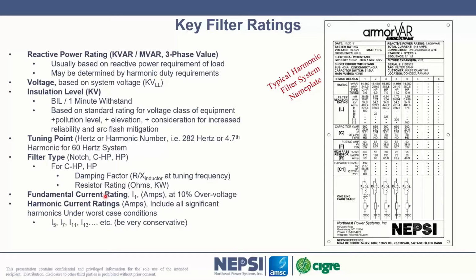What is the fundamental current rating of the filter? Well, it's basically the reactive power divided by the square root of 3 divided by the voltage. But we want to state what the fundamental current is, assuming a 10% over voltage. Don't forget the utility is going to supply a voltage, and typically it could be plus minus 10%. So all your ratings should assume a 10% over voltage condition in the system.